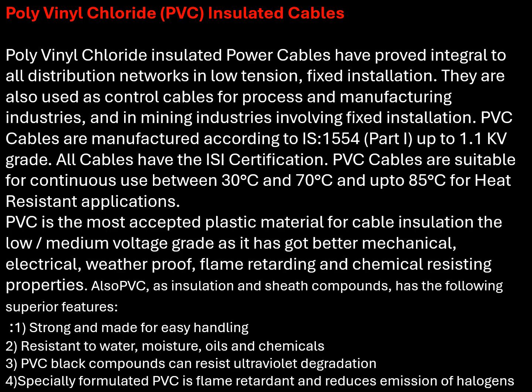PVC cables are suitable for continuous use between 30 to 70 degrees Celsius and up to 85 degrees Celsius for heat resistant applications. PVC is the most accepted plastic material for cable insulation for low and medium voltage grade, as it has better mechanical, electrical, weatherproof, flame retarding and chemical resisting properties. It is superior because it is strong and made for easy handling, resistant to water, moisture, oils and chemicals. PVC black compounds can resist ultraviolet degradation. Especially formulated PVC is flame retardant and reduces emission of halogens.